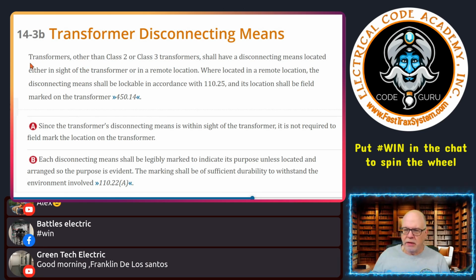All right. Now, we're talking about transformers other than the class 2 or class 3 transformers, which are smaller typically. So we're talking general power transformers like you probably deal with every day. A class 2 or class 3 transformer is typically found in a lot of equipment, where the secondary side runs a very limited power source to a limited load. A good example of a class 2 would be a doorbell transformer. Just remember that class 2 and class 3 typically have limited output compared to a traditional power type transformer.